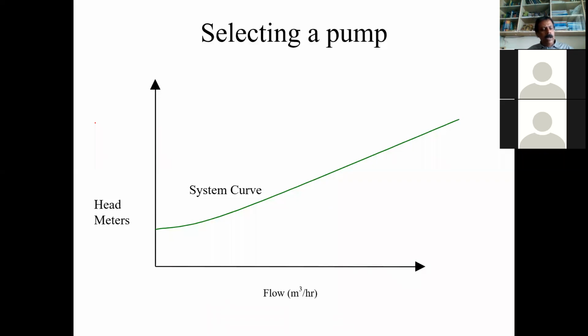We normally ask all the users how much is the requirement for water in different areas. Let's take an example of a centralized cooling water system. The cooling tower water is going to different parts of the plant. Section A, section B, section C, like that. We ask each section how much water do you need. So each one calculates the water requirement. So section A calculates maybe 20 meter cube, but they're not going to say we want 20 meter cube. They would like to keep some margin. So they say 30.